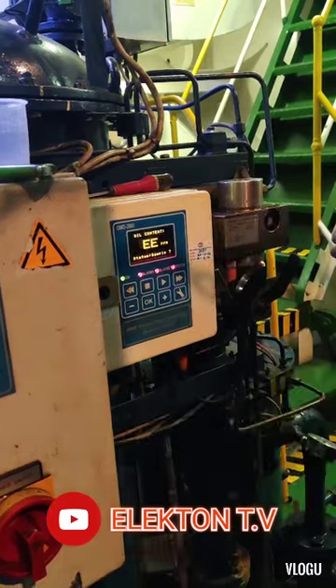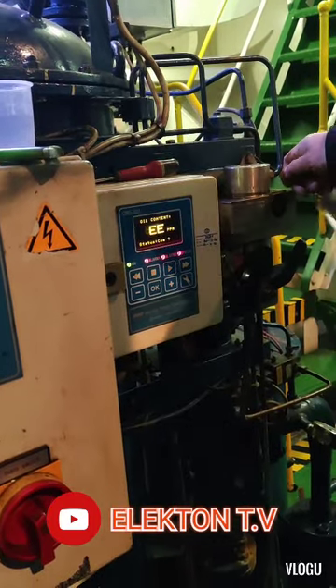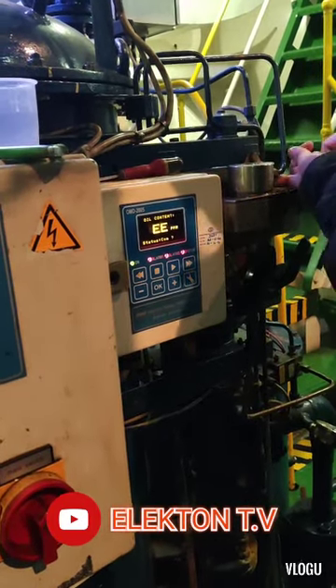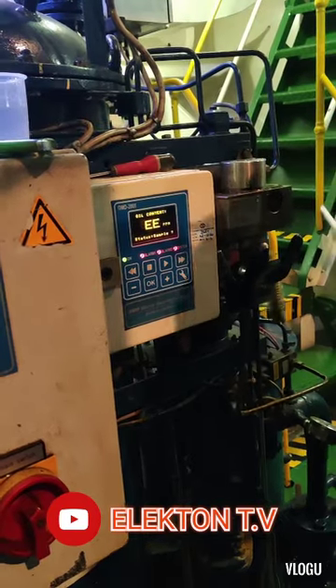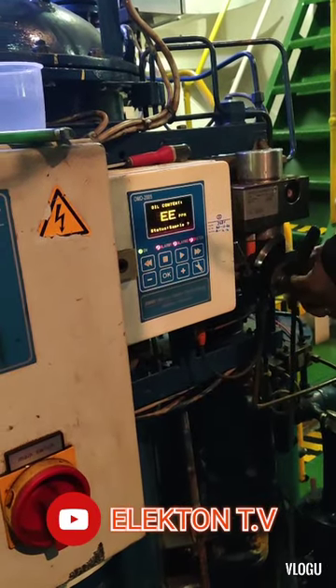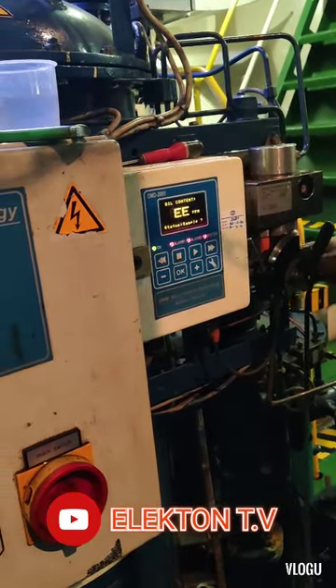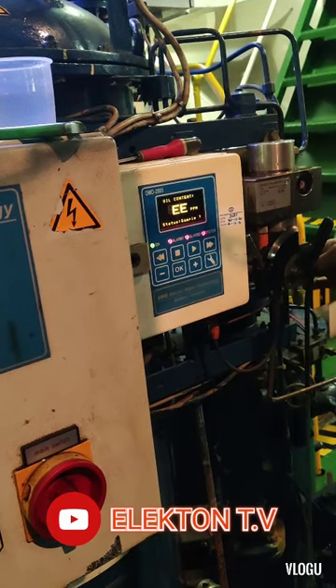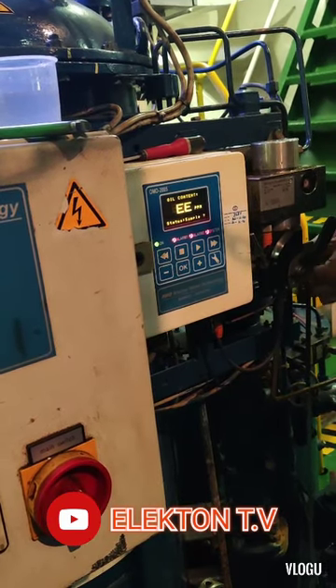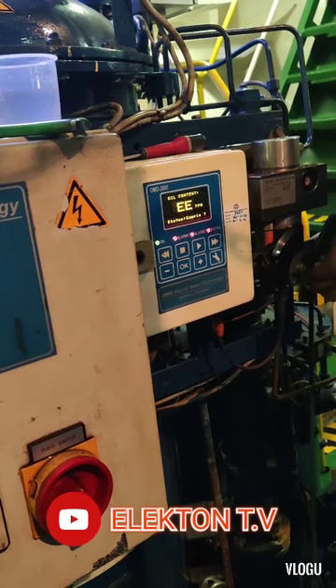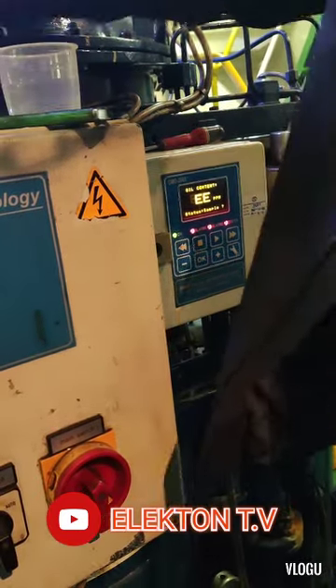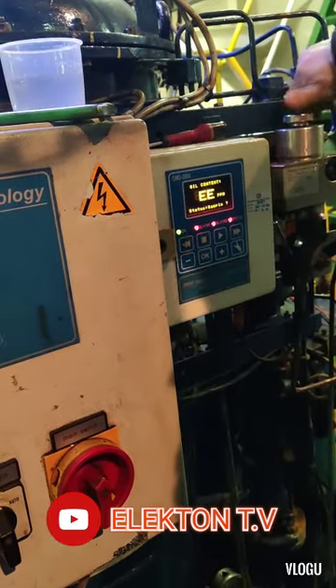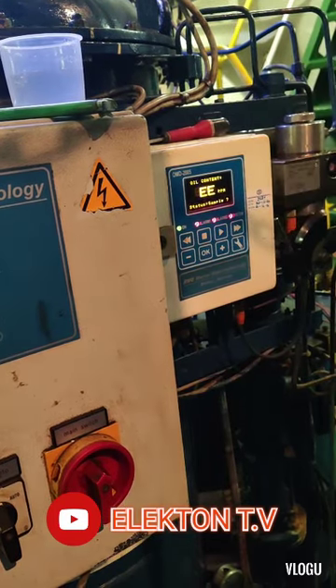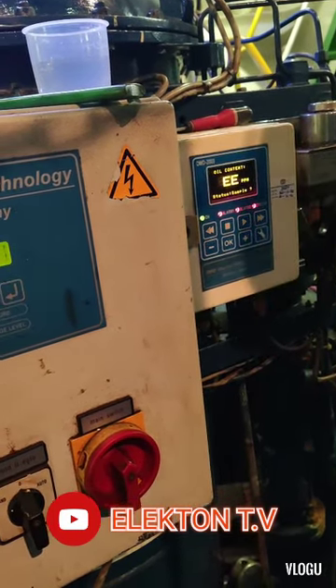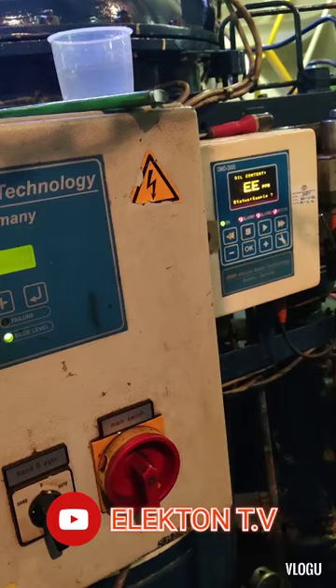Even when the monitor gives a reading of more than 15, the normal behavior is that if the sensor gives a reading of more than 15 ppm, the oily water separator system automatically stops and gives an alarm on the engine control room. And that was the problem.